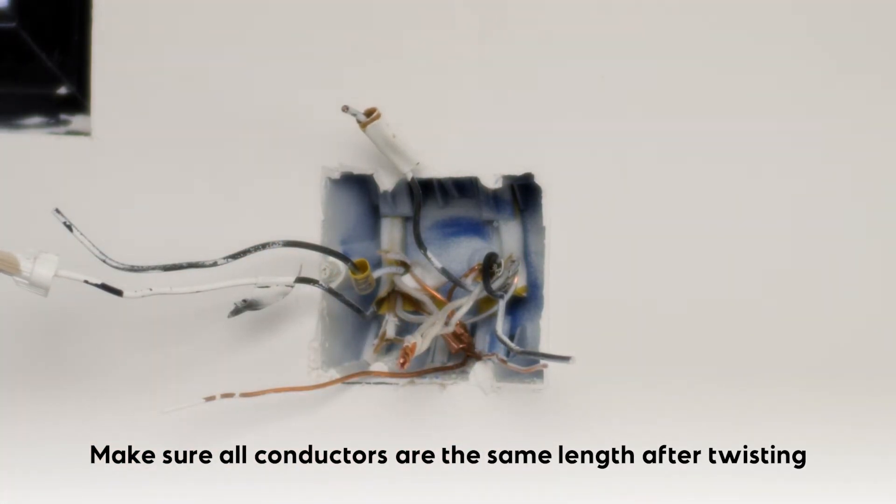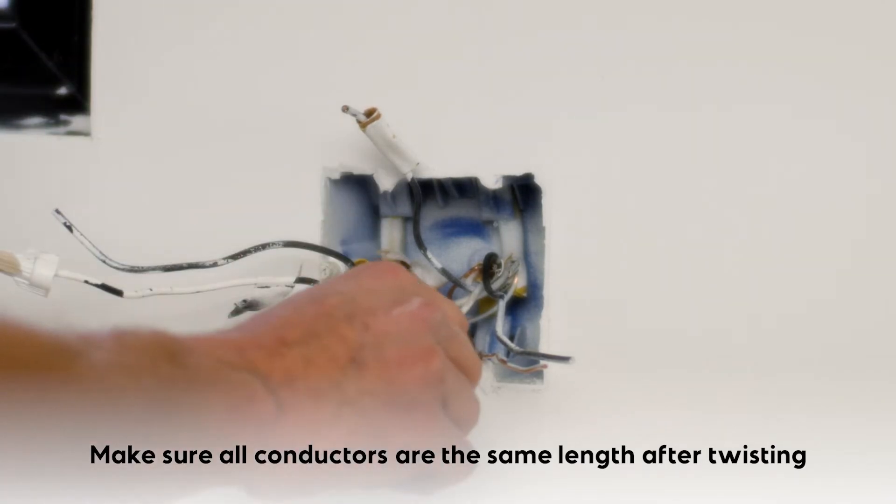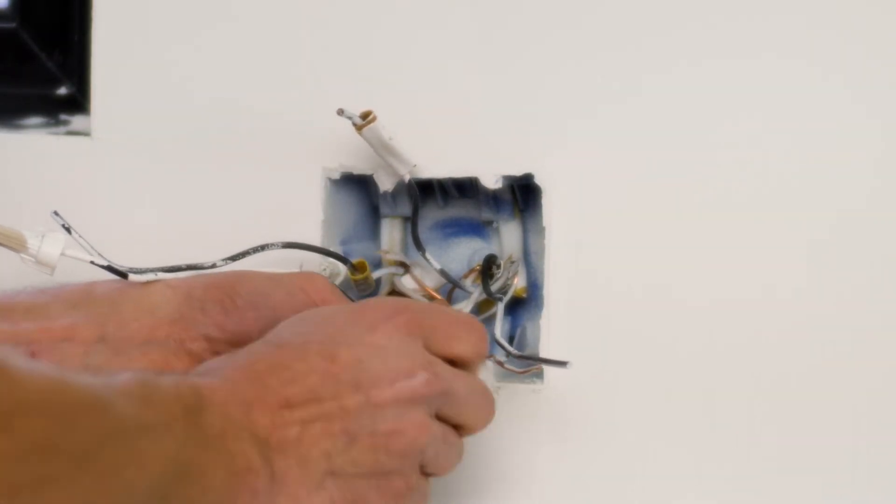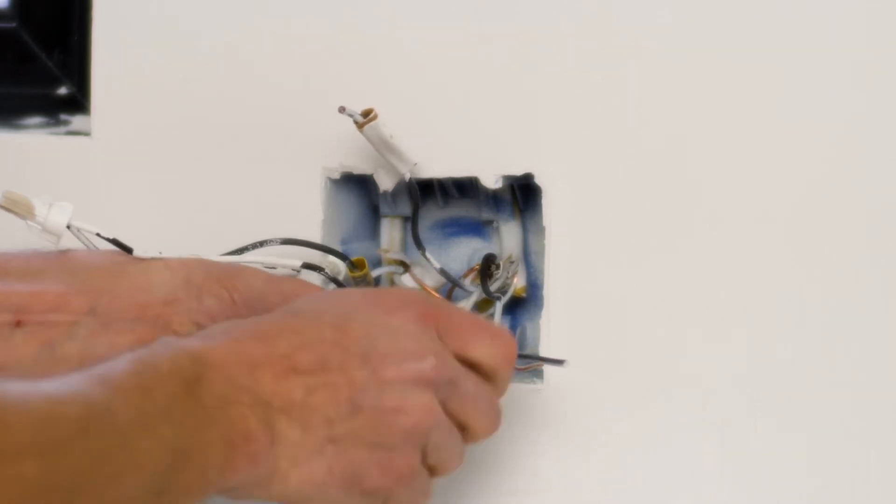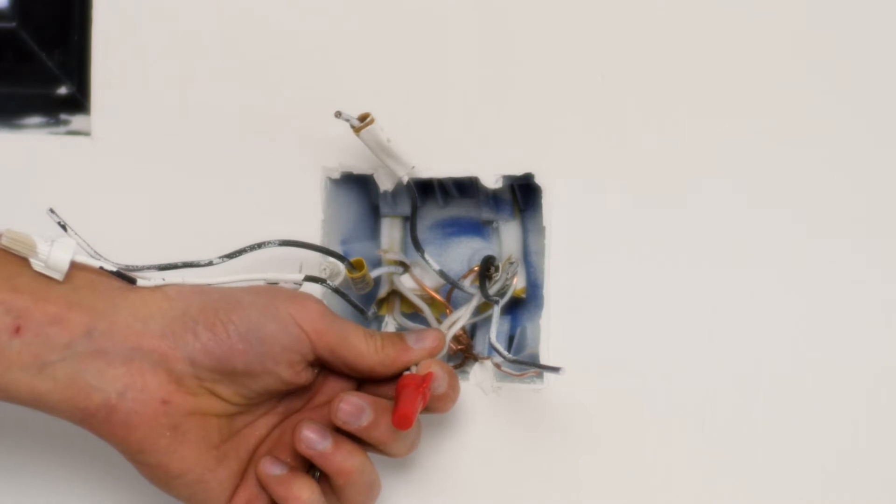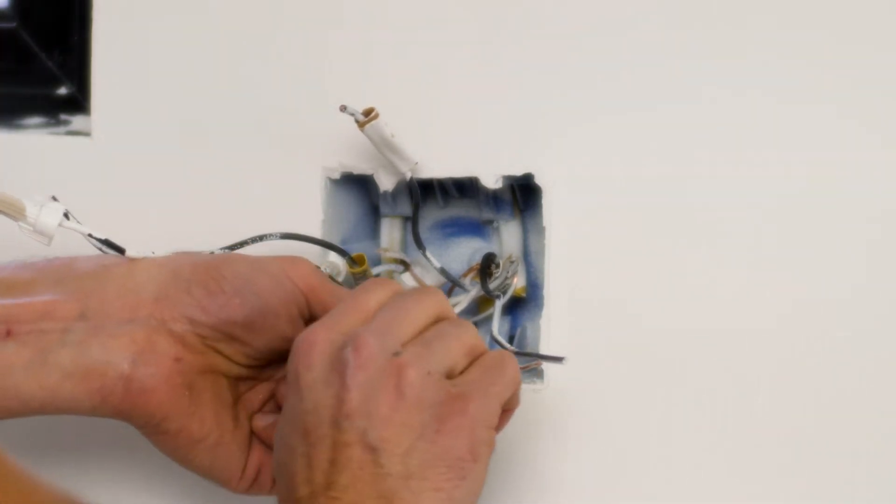In this case, because I have four number 12s, I'm using a red ideal wire nut. I'm twisting to the right. Always to the right. Your pre-twist is always to the right because your wire nut installs to the right. That's the tightening method.